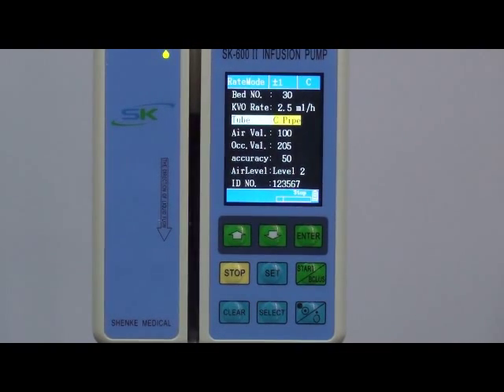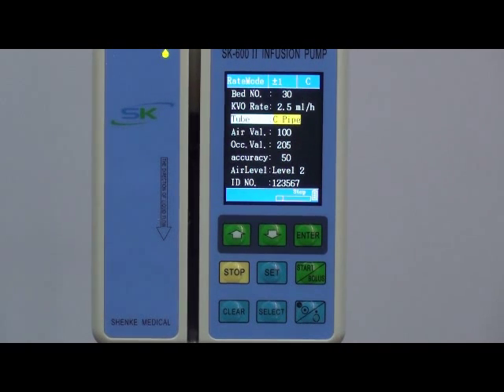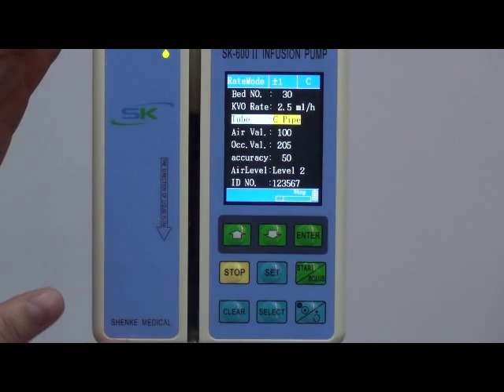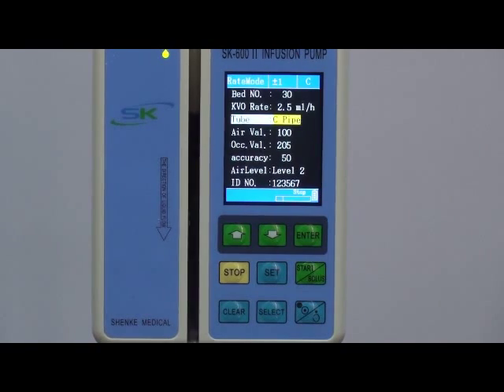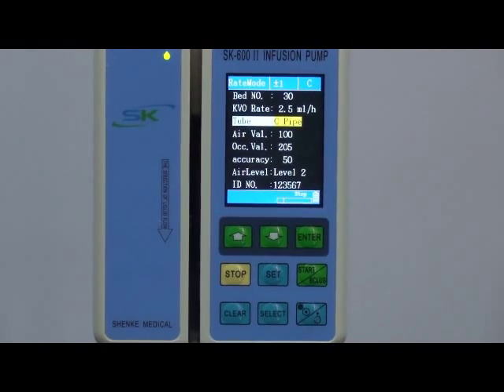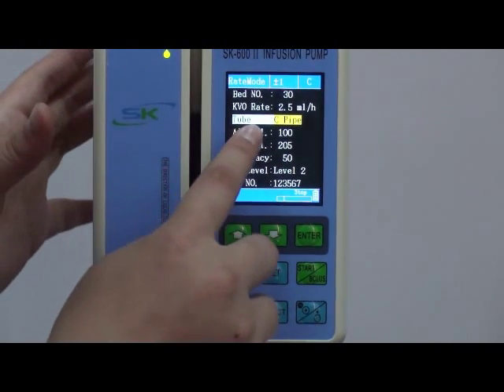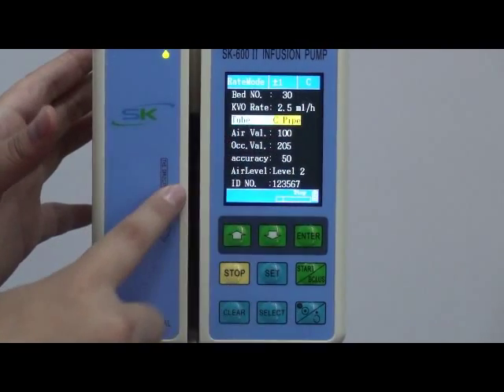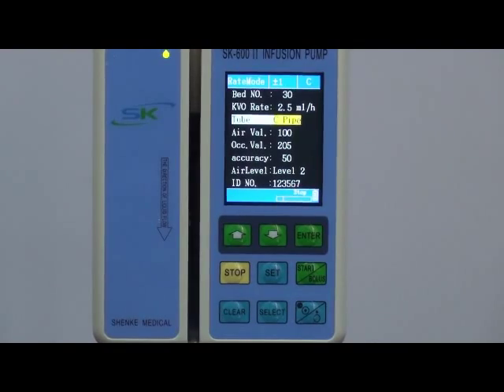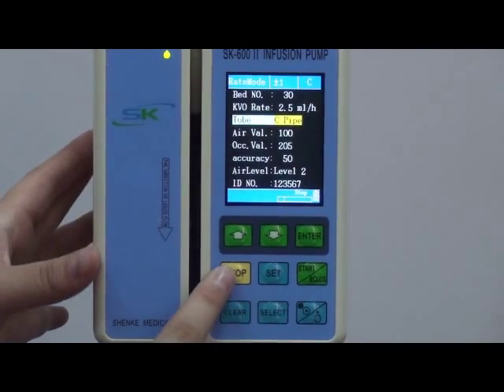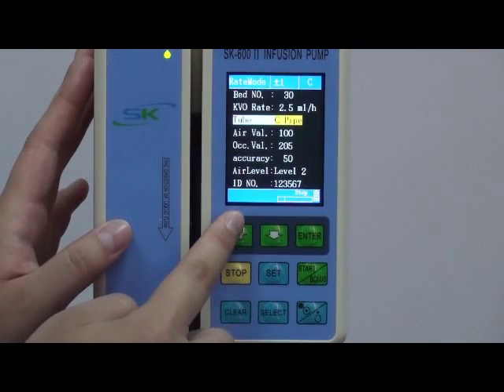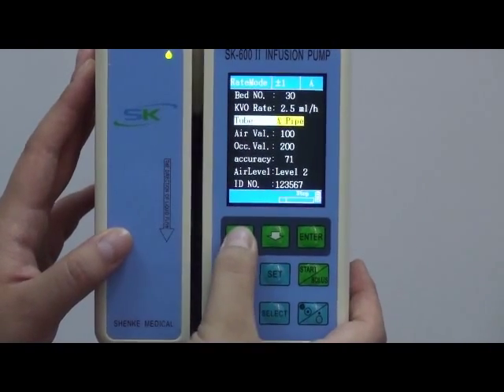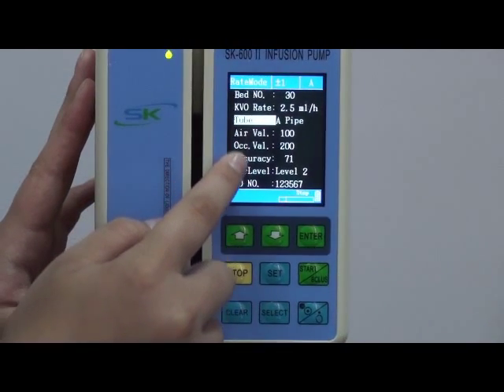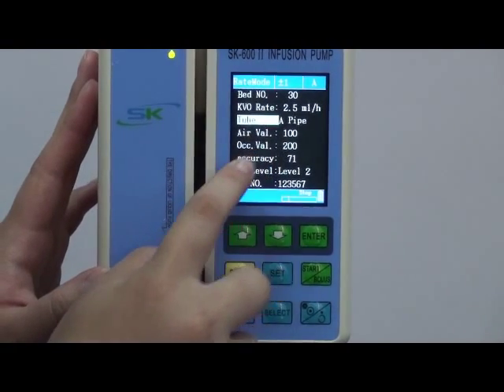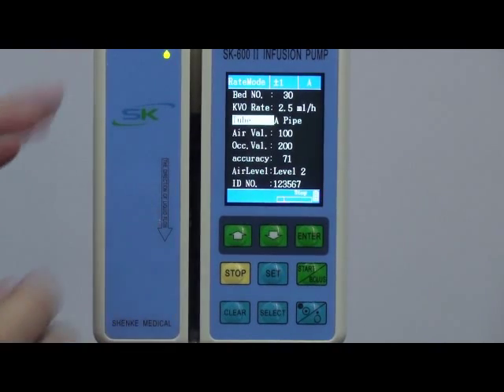In order to prevent those problems and extra work for the nurses, we came up with a solution. That is to ask our infusion pump to memorize 3 different brands' IV set parameters. That is what you are looking at right now. Tube. Pipe A, B, and C. You could change them. For example, the nurse wants to use pipe A at 9 a.m. So she starts the pump. Press stop and select keys together to enter into this interface and choose tube. Choose A. Then all the parameters, for example, air value, occlusion value, and accuracy will be exactly for pipe A.